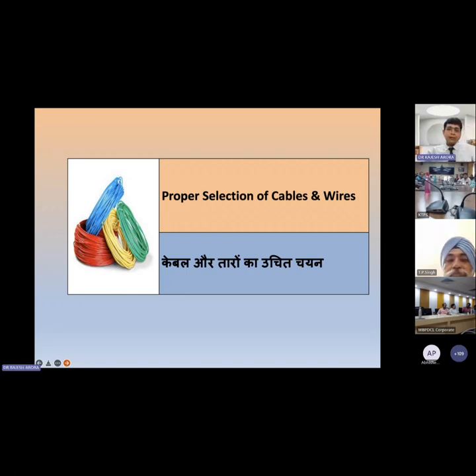Never overload your cable. Proper formation of circuits and proper distribution of load are a must to avoid fire because of these cables and wires. When I say proper selection, the short circuit capacity of that wire and the basic insulation level of that wire play a very important role. Be careful. With these small tips, there will be a big change in the system.